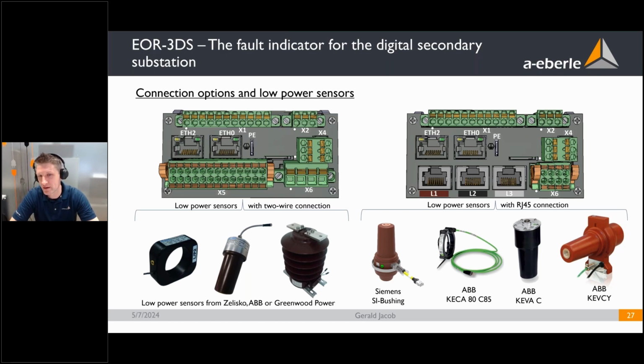From ABB you always also have the possibility to install separate sensors, for example here a voltage and a current sensor. These sensors come also with an RJ45 connector, can be connected with a special adapter to one RJ45, and then you have once again on one RJ45 current and voltage measurement of one phase. So of course, our device wants to measure all three phases, as you can see, L1, L2, L3. So in a compact switchgear station in each field, there are either 3 of these Siemens SI bushings installed or 3 of these ABB bushing sensors installed, or 3 current sensors and 3 voltage sensors in one field. Okay, so these are low power sensors, also with class 0.5 and RJ45 connection.